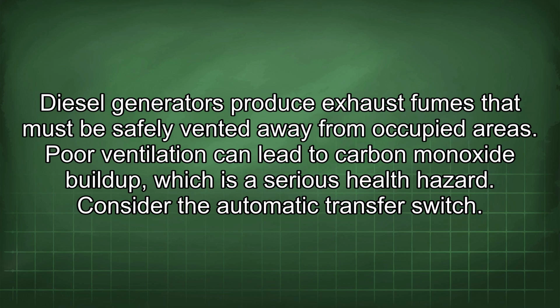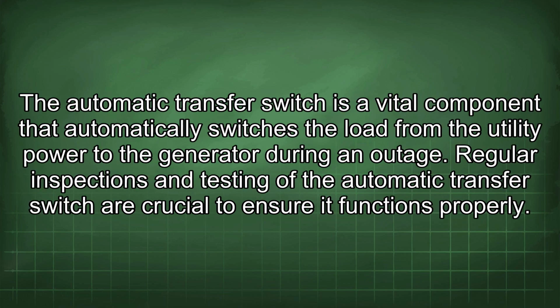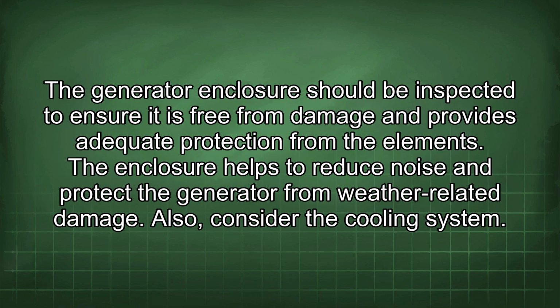Consider the automatic transfer switch. The automatic transfer switch is a vital component that automatically switches the load from the utility power to the generator during an outage. Regular inspections and testing of the automatic transfer switch are crucial to ensure it functions properly. The generator enclosure should be inspected to ensure it is free from damage and provides adequate protection from the elements. The enclosure helps to reduce noise and protect the generator from weather-related damage.